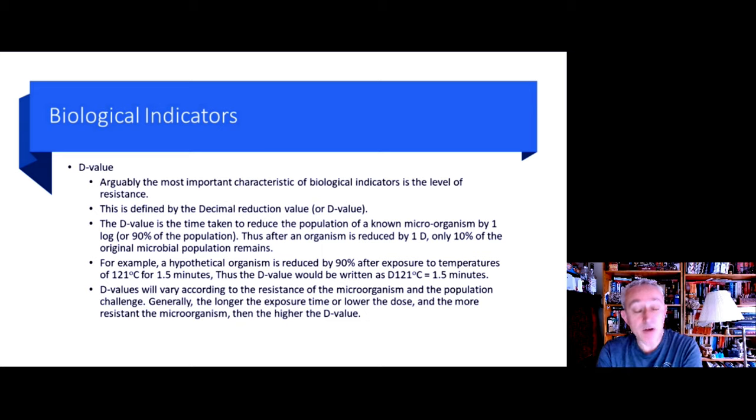So if we were to purchase biological indicators with a D value at 121 degrees Celsius stated at 1.5 minutes, then this becomes the standard for operating an autoclave device. This means that our spores on our spore strip will be reduced by 90% after exposing the biological indicators and our autoclave load for 1.5 minutes at 121 degrees Celsius. And it then follows, with each successive 1.5 minutes, the microorganisms decrease by a further 1 logarithm.